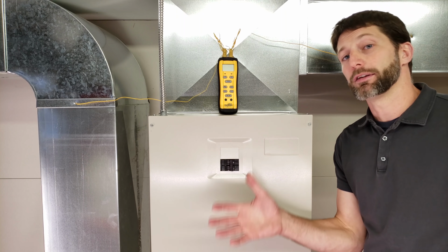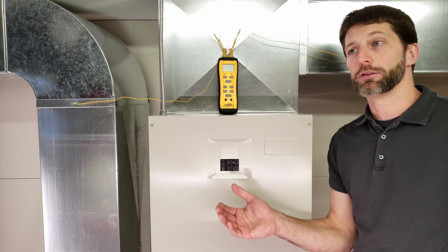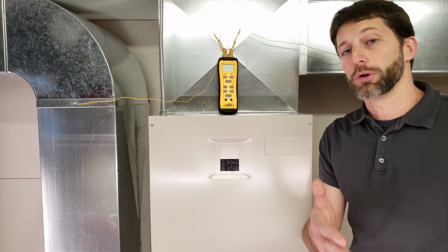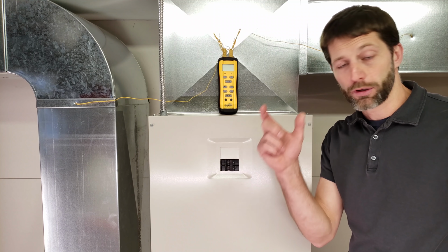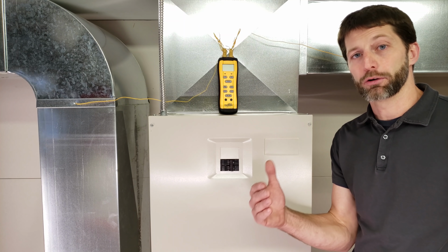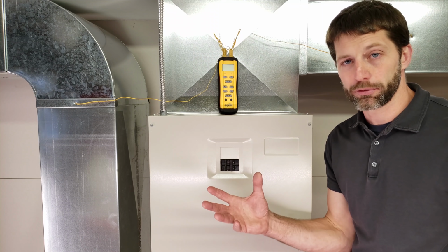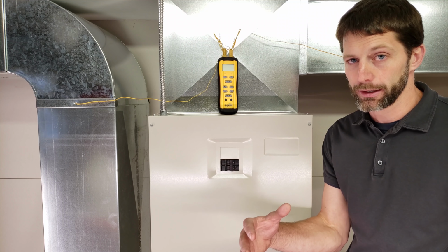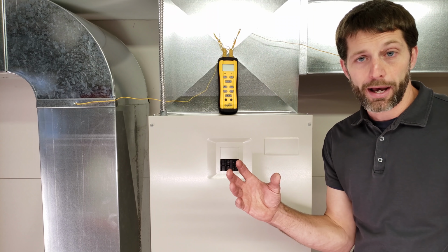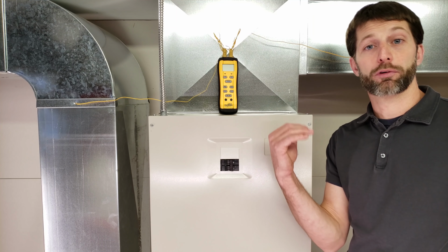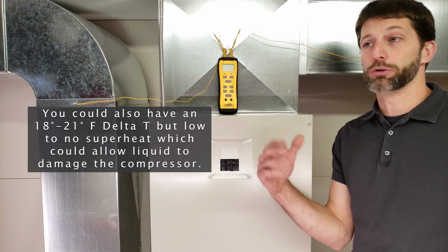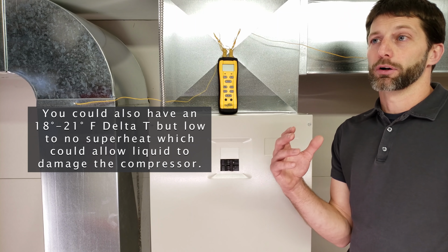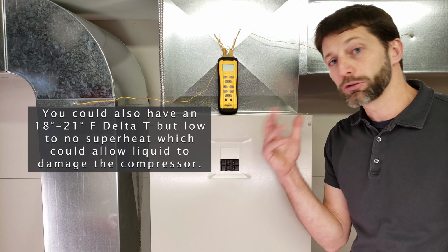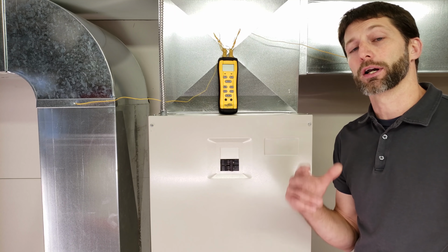So you may have 18 to 21 degrees, but just because you have an outdoor unit that has 24,000 BTUs on the model number, that does not mean that you're removing 24,000 BTUs of heat from the building. So you may be at a lower capacity. So maybe your refrigerant charge is low, but also your airflow is low. So that could be an issue as well, even if you do have the correct Delta T. So you really want to monitor the total superheat and the subcooling when you're checking the refrigerant charge.